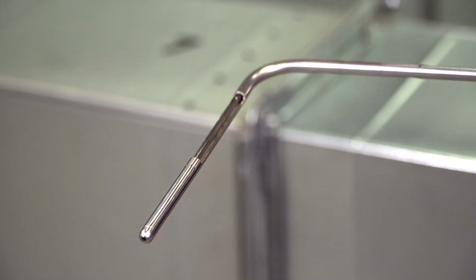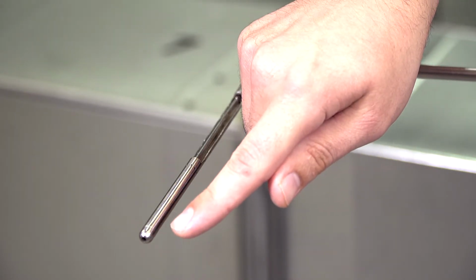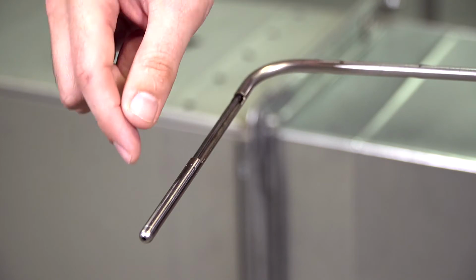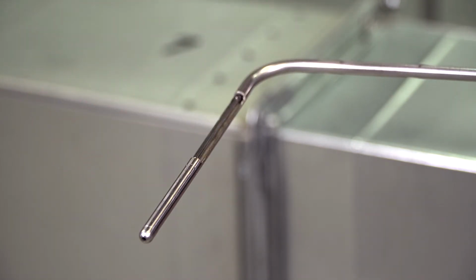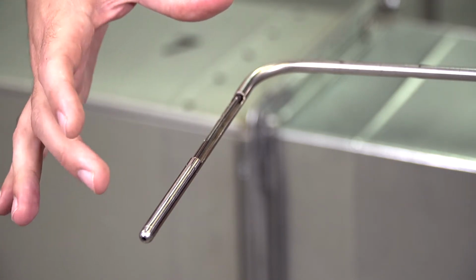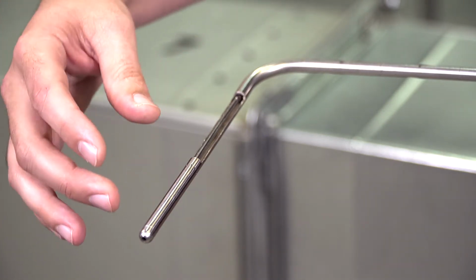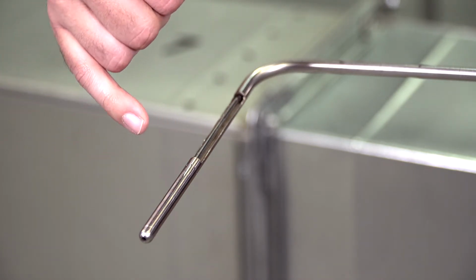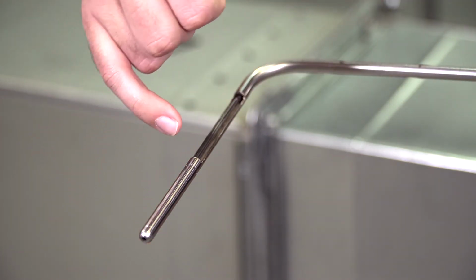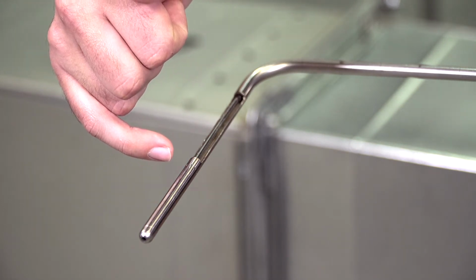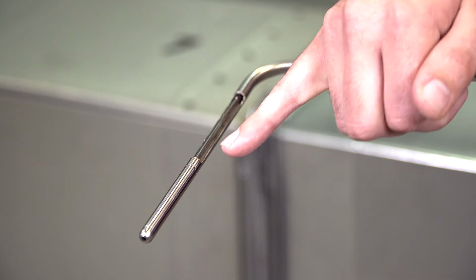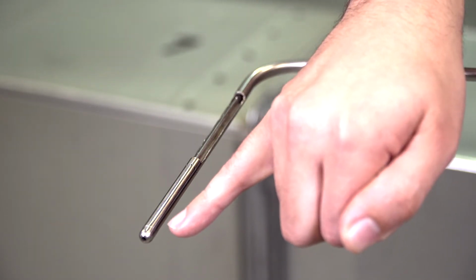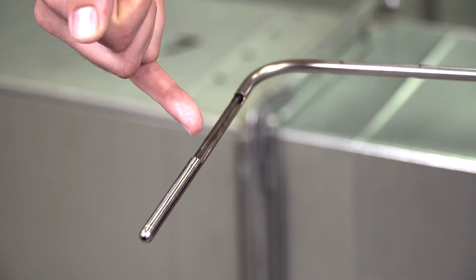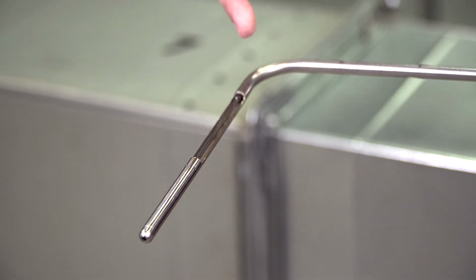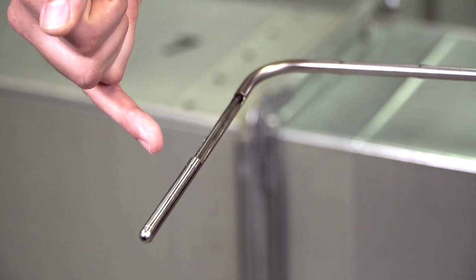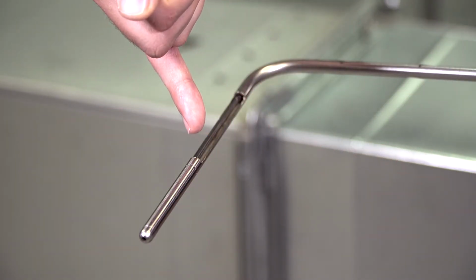Okay, so let's discuss the pitot tube. Here at the tip we have what's measuring the total pressure, and this is the end that gets placed directly in the airstream. The pitot tube is constructed with a tube inside of a tube, such that the radial holes on the outer tube measure the static pressure. The total pressure runs through the inner tube along the pitot tube, and the radial holes measure the static pressure on the outside of the inner tube.